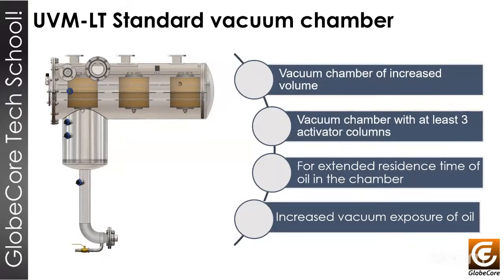Okay, one of the more interesting things in our machines is the vacuum chamber. This vacuum chamber is really special. You can see here 3 different columns inside of this vacuum chamber. These 3 different columns have the function of dividing the flow of oil inside. That will help us to expose the oil for more time to the vacuum. And when you have more time the oil in contact with the vacuum, you will have better results with the dehydration and the degassing process.